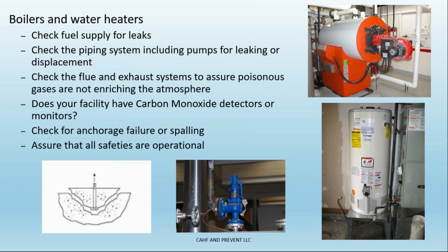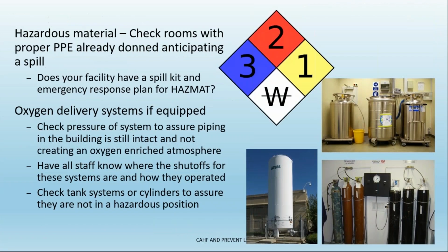Make sure that there are no poisonous gases that are going to be enriching the atmosphere. Have a carbon monoxide detector. Does your facility actually have a carbon monoxide detector? Have your staff been trained on how to use a carbon monoxide detector? Make sure all of these systems are addressed in your emergency operations plan. Check your anchorage for any kind of failure or spalling, and assure that all the safeties are operational on all the different water heaters and boilers, steam boilers, and all those other types of systems.